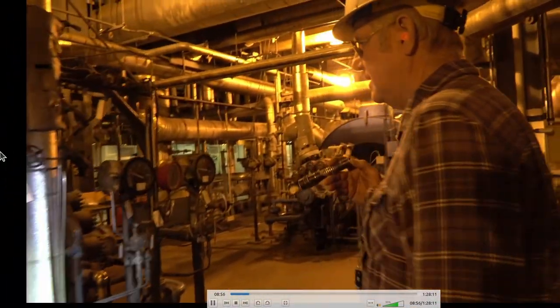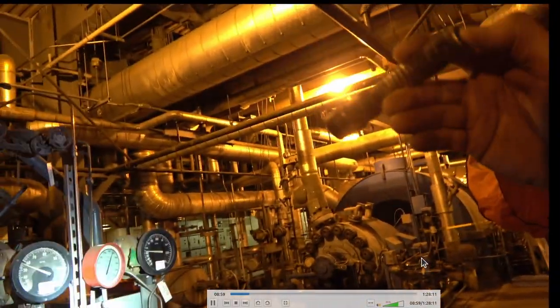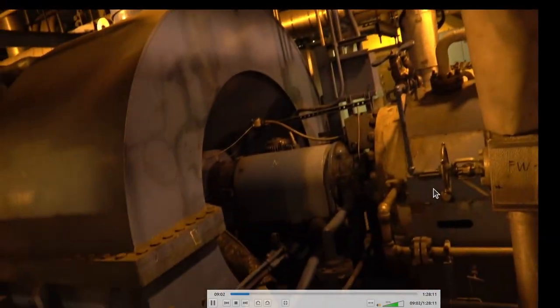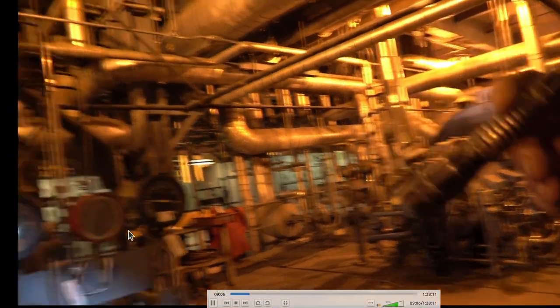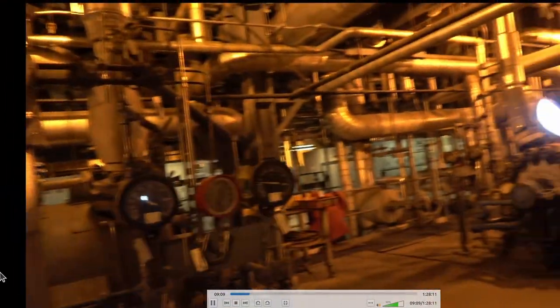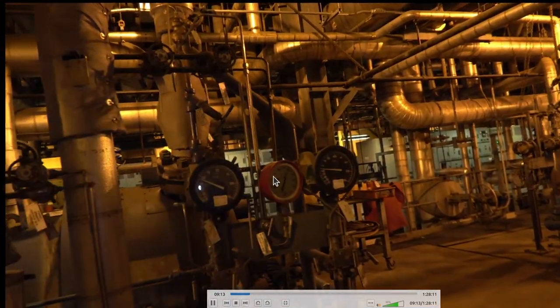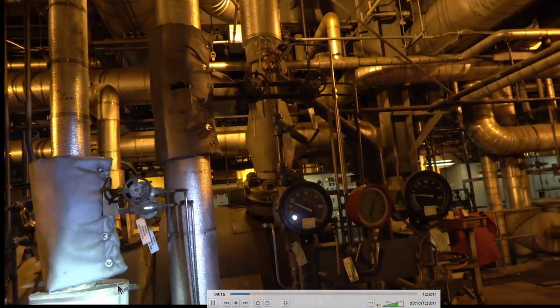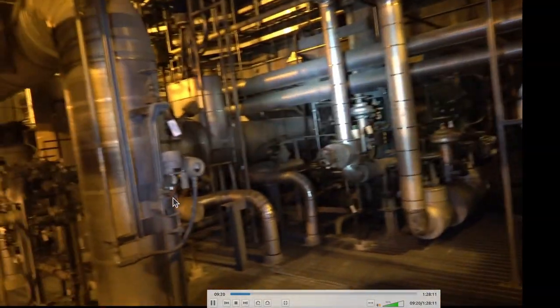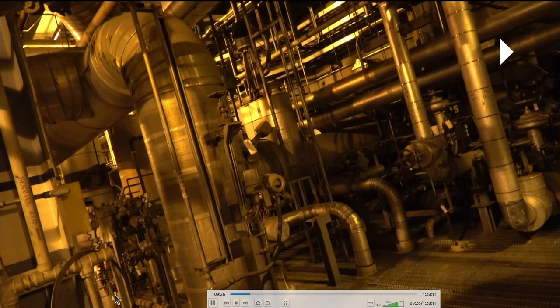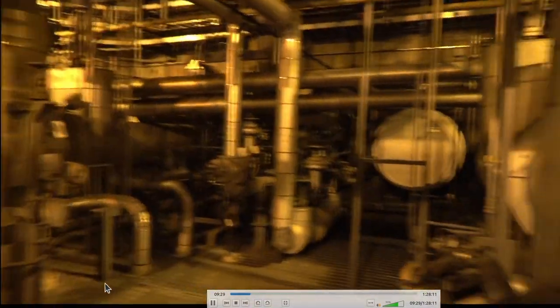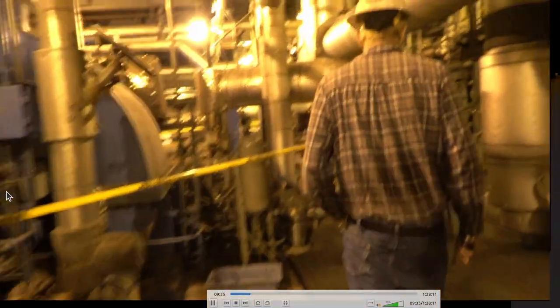This is the high-pressure feed pump. There are two pumps in this plant. Your turbine sits here and exhausts down to your main turbine surface condenser. These are the sealing pressure gauges — this pump is sealed with water. It takes the booster pump flow and feeds it into the seal; part goes into the pump and the other part leaks out. Then you have cold water feeding in there, and that water goes to the surface condenser, sealing the turbine feed pump.